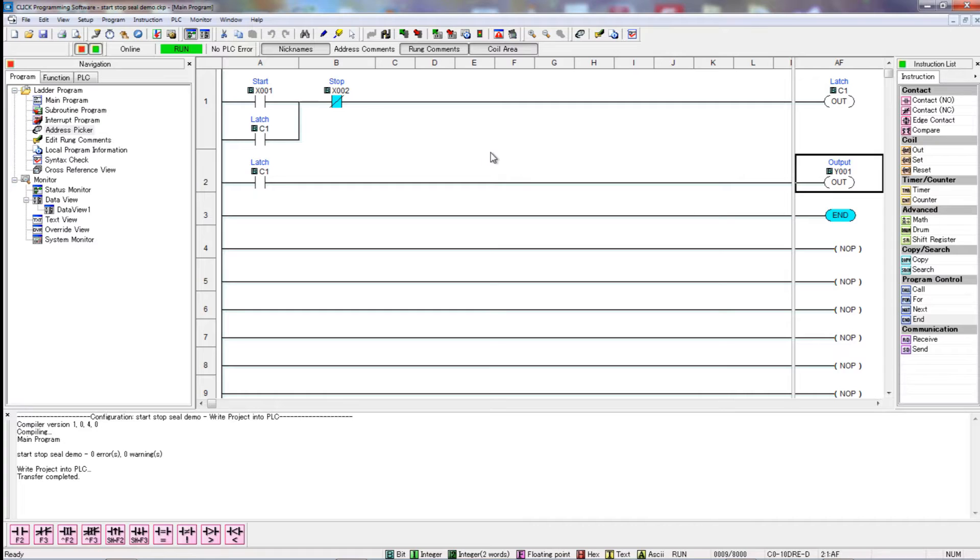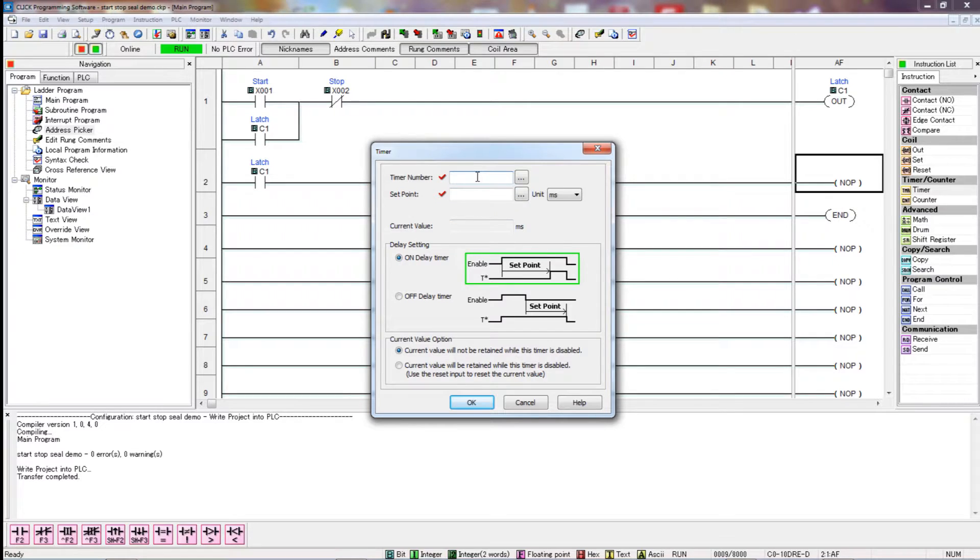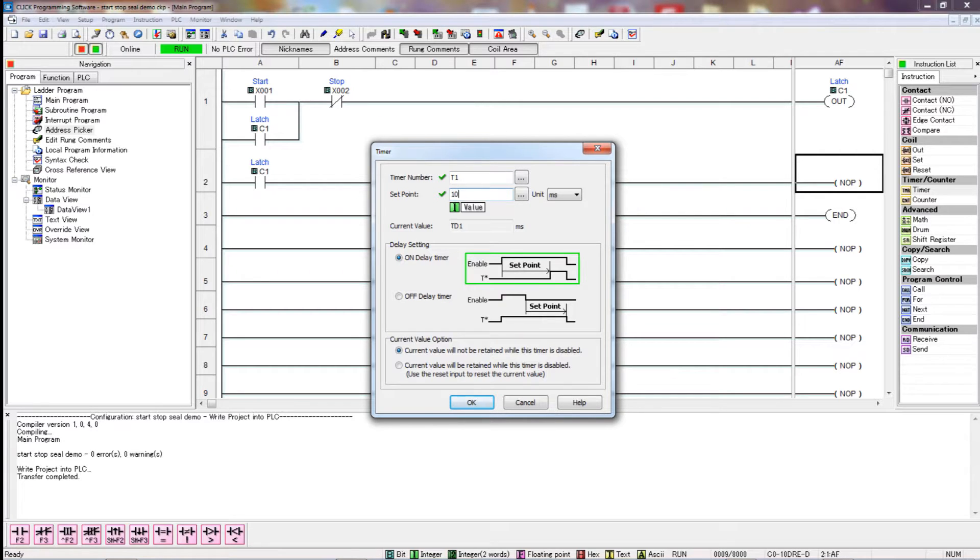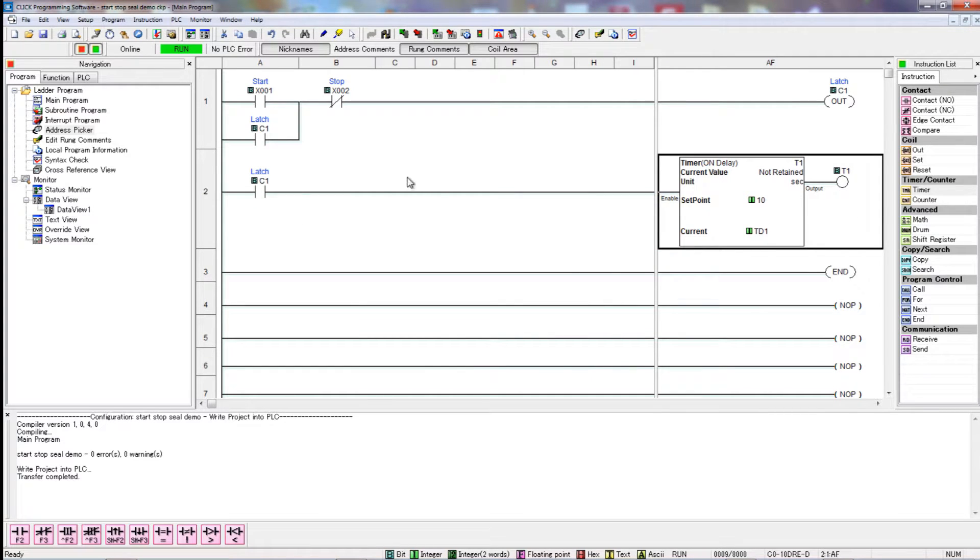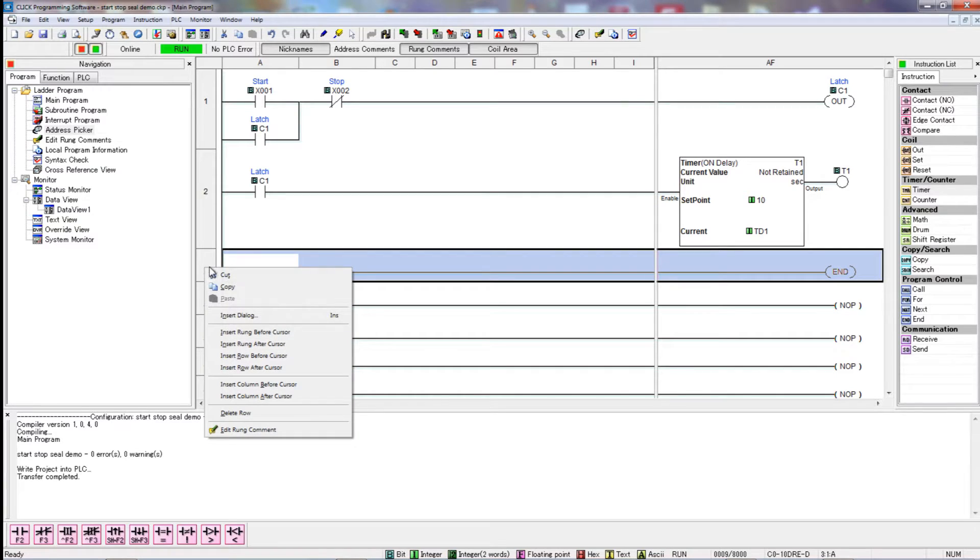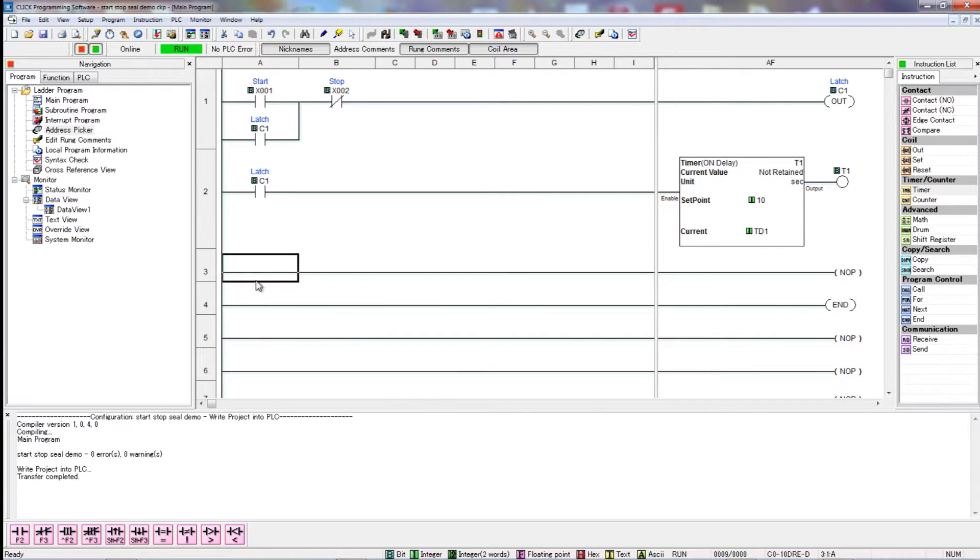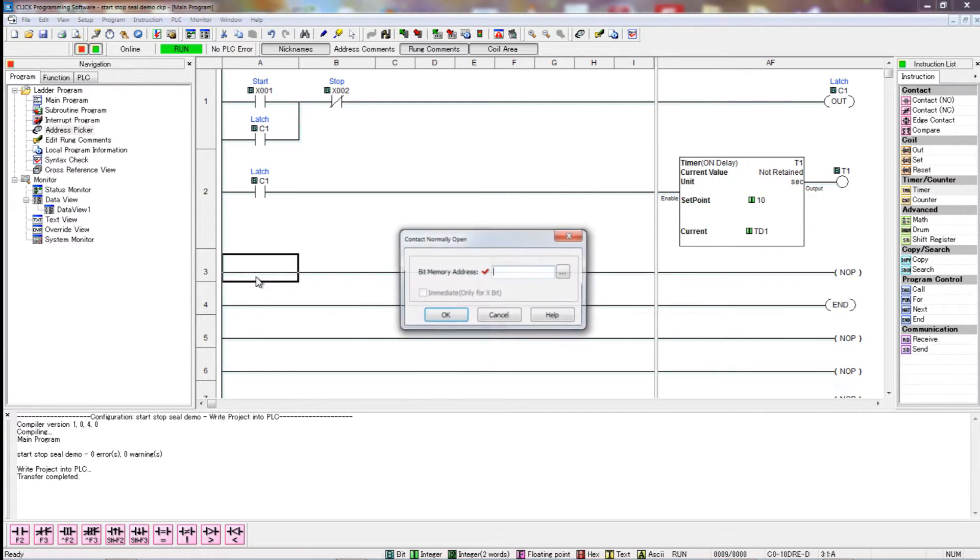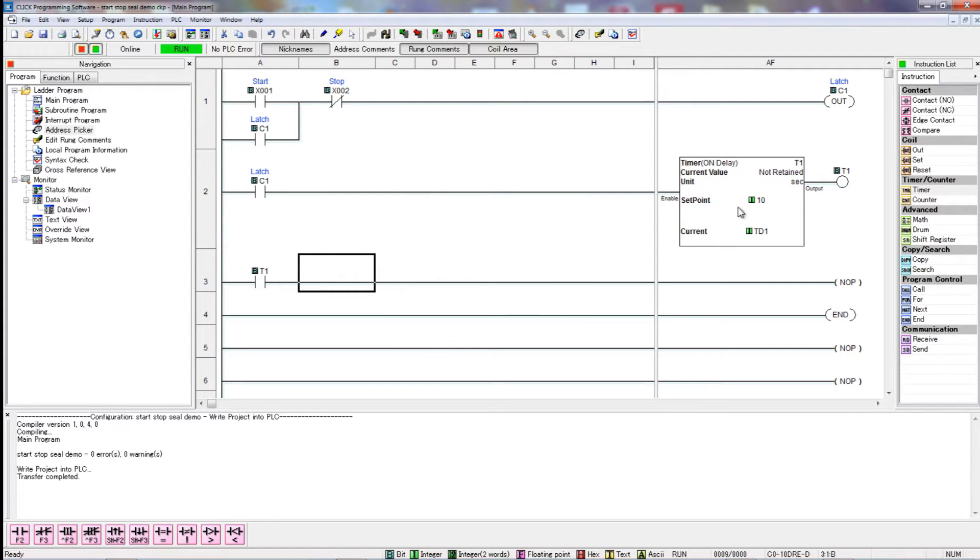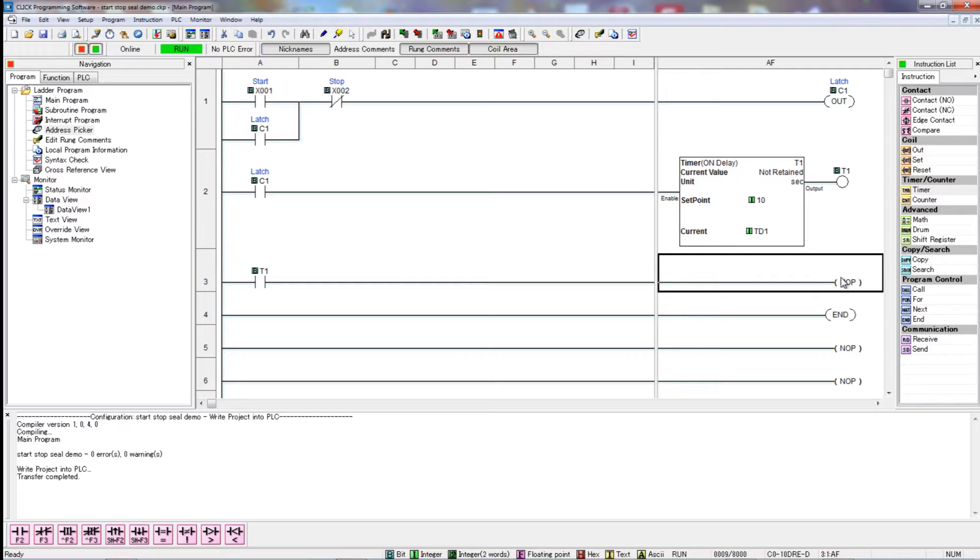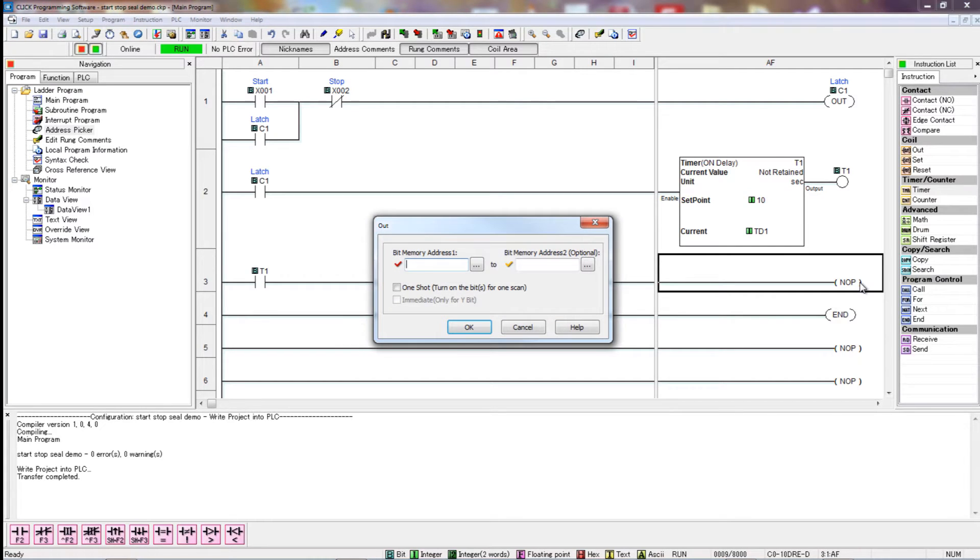So, let's expand this a little bit further. Now, instead of this output, maybe I'll delete him out of there. I want to use a timer. And this timer is T1, just because this is a new program. And I know T1 has not been designated yet. And we're going to turn it on for, let's say, 10 seconds. We change our units to seconds. I've got this set as an on-delay timer, because I want it to come on after a certain setpoint. And the current value would not be retained. This means if the timer is off, it doesn't retain its current count up if it counts a few seconds and then turns off. And then I'm going to, once again, select this to insert a rung. And here I'm going to put a normally open contact, T1. Now, T1 is the output of our timer. So, after 10 seconds, or whatever the setpoint is, this timer will become active and turn on. And then we can turn on our favorite output, Y1.